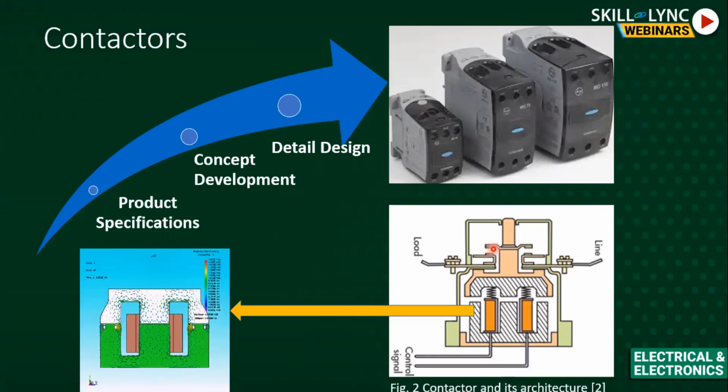So this is how we do iterations and come up with what we finally need. This phenomenon of reopening is known as double pickup in the industry. So it is not an intended phenomenon. So we change the coil parameters again and try to achieve what is really needed.